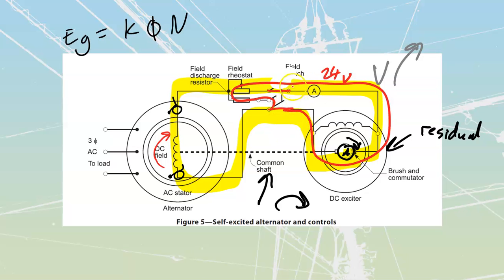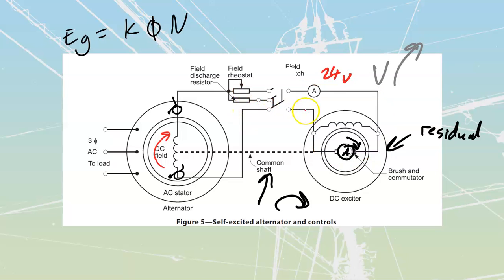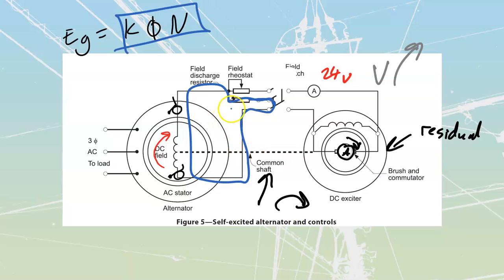Then as we continue to open the switch, it's going to break this contact. As it does so, this stays intact over here, and because I'm still rotating, this is going to be closed across here, so that any residual magnetism that is causing me to generate voltage is not going to give me a ridiculously high value of voltage. Really, we're trying to avoid inductive kick from these.